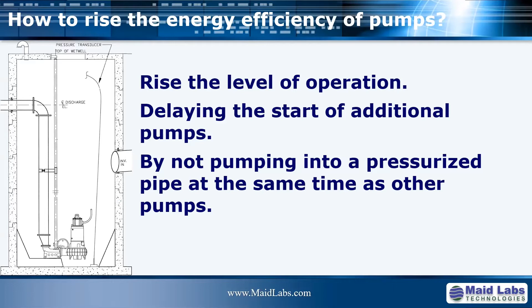Then you have the lag level that should be a little bit above the lead level in case the flow coming in is just greater than the capacity of the actual pump running. And then you have a high alarm level, which means that both of those pumps working together is not enough to compensate for the actual flow coming in. Or if the pump didn't start because the PLC would have a problem, then it should override all of this and start all the pumps. Okay, that's another reason why. So this is how it works.